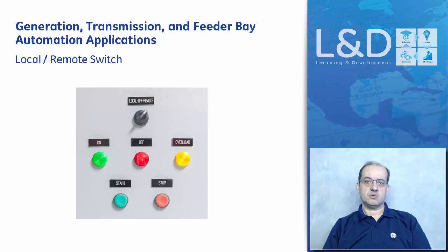When the master local remote switch is in the local mode position, the data concentrator or the RTU, remote terminal unit, and all distributed units will be switched to local mode, hence disabling all control functions at the data concentrator, RTU, and all distributed units. When the local remote switch is in the remote mode position, the data concentrator, RTU, and all distributed units will be switched to remote mode, hence enabling all control functions to be performed normally at the data concentrator RTU and all the distributed units.